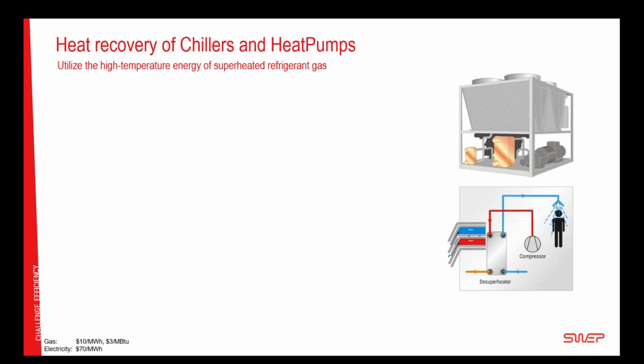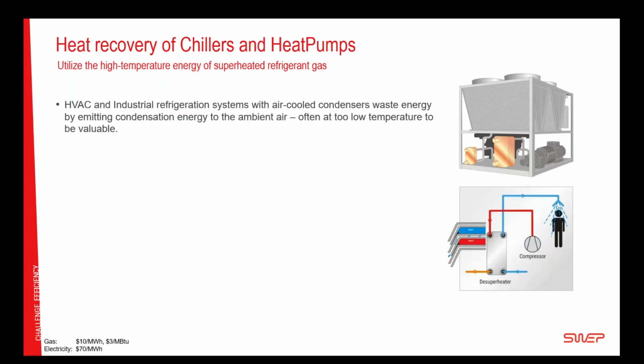Heat recovery of chillers and heat pumps. Chillers, they are everywhere. It's much more common to find air-cooled chillers and heat pumps rather than water-cooled. And since they are optimized to operate at a low condensing temperature, because that gives a higher EER or COP, the temperature of the energy you get out from the condensing energy is so low that it's rarely considered to have any value.